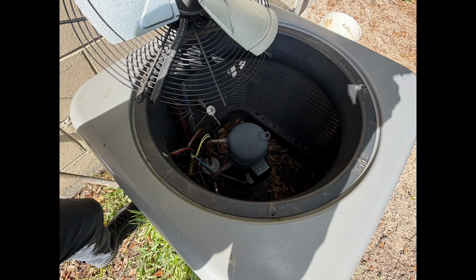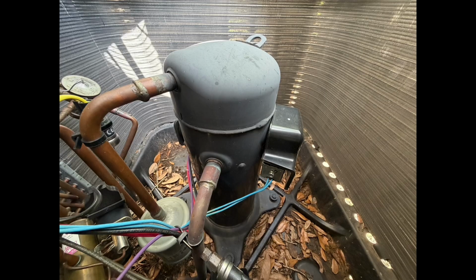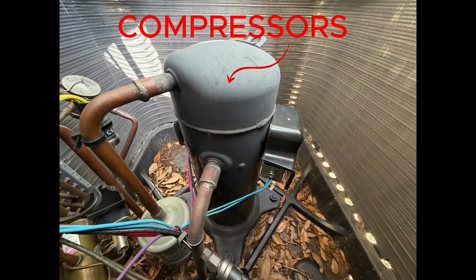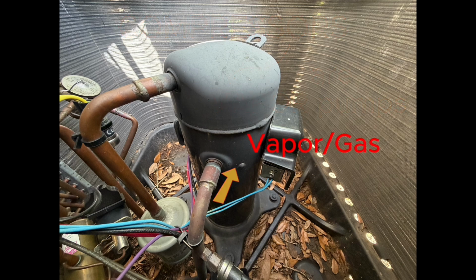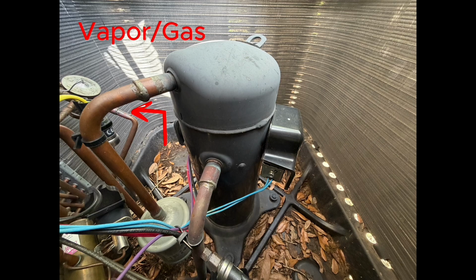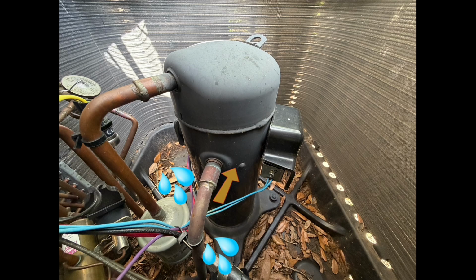Typically, compressors will look like this and will be found inside of the outdoor equipment. An extremely important thing to understand about compressors is that they are vapor pumps. This means that they take vapor or gas in and they discharge vapor or gas out as well. Under no circumstance should a compressor be taking in liquid.